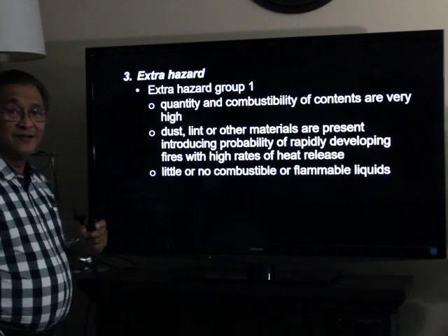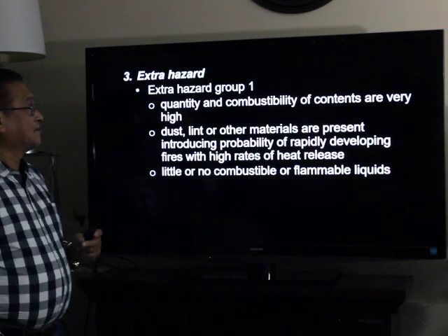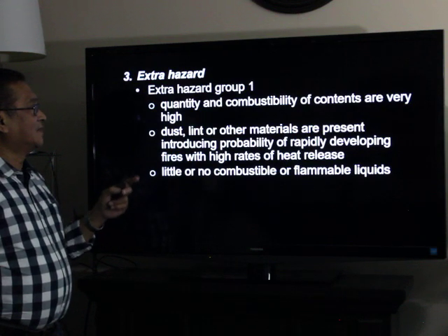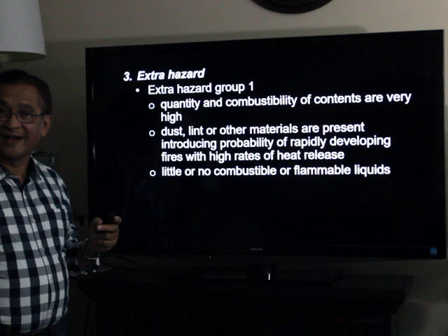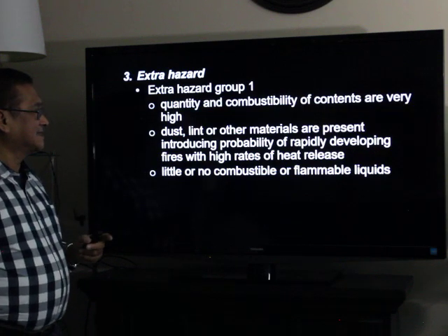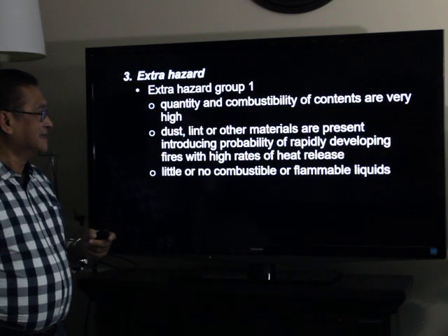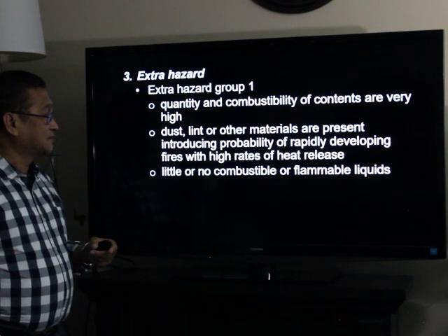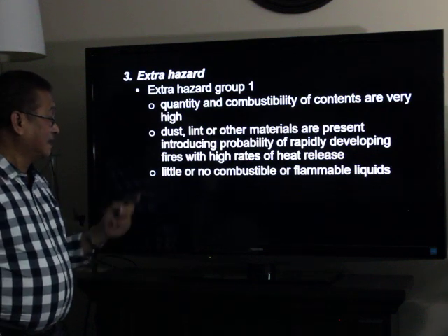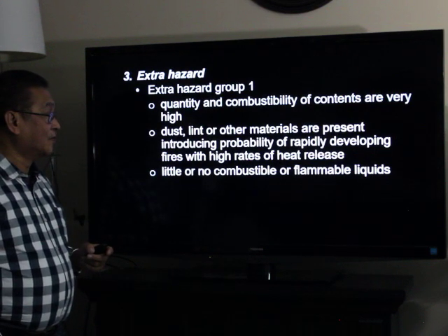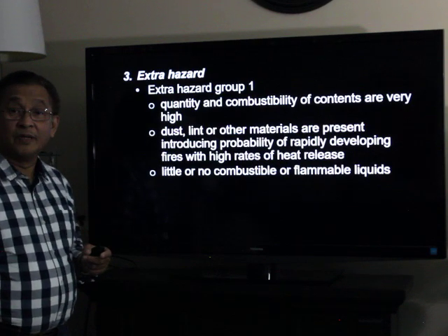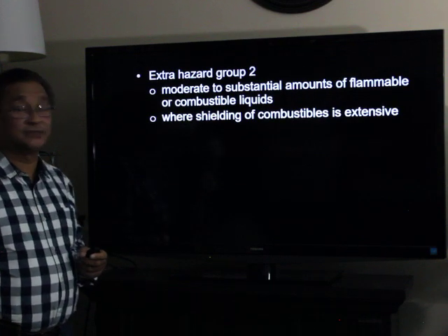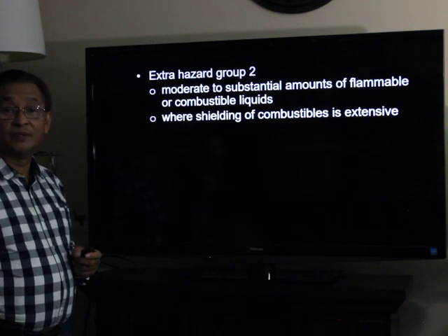Extra hazard also has two groups. Extra hazard group one: the quantity and combustibility of contents are very high; dust, lint, or other materials are present, introducing the probability of rapidly developing fires with high rates of heat release, and little or no combustible or flammable liquids. Extra hazard group two: moderate to substantial amounts of flammable or combustible liquids, and shielding of combustibles is extensive.